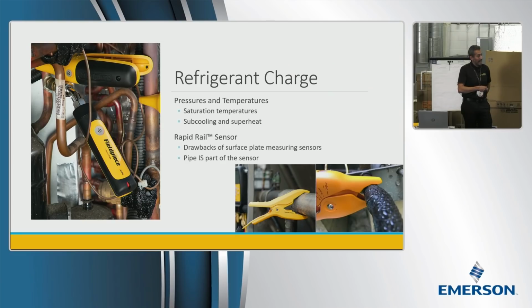In the real world, on these pipes, there's going to be a lot of stuff that affects the temperature on the surface of that pipe. Gunk from insulation that's left behind, corrosion, if the pipe is wet, if you're taking a measurement in direct sunlight and it's hitting the plate of your thermocouple, all that's going to adversely affect your temperature measurement and not give you the most accurate reading. And that's important because that could be the difference between calculating 8 superheat versus 8 subcooling versus maybe 4 or 5, which is a big deal. When we're trying to give the customer the best information for them to make the correct decision for them and their home, we've got to give them the most accurate data to do that.